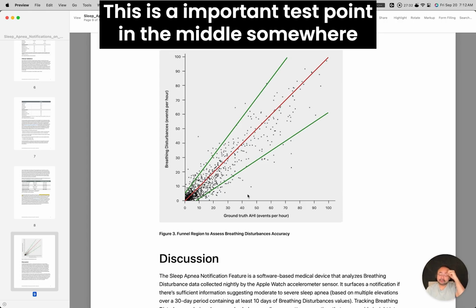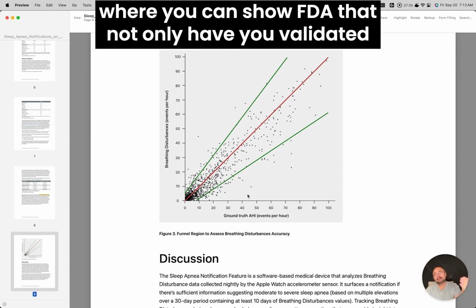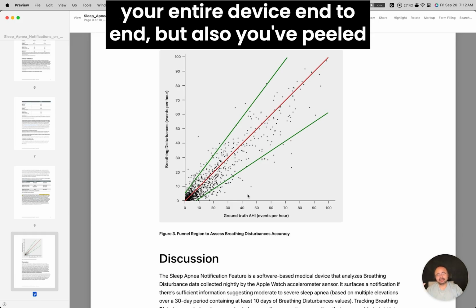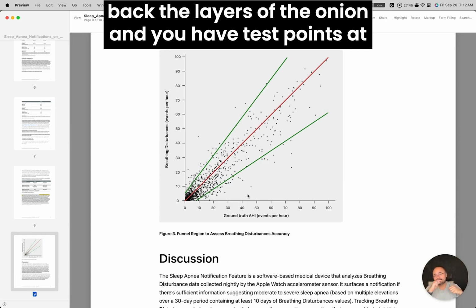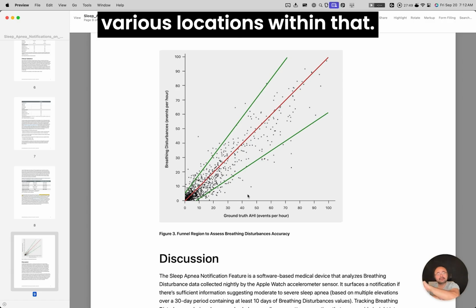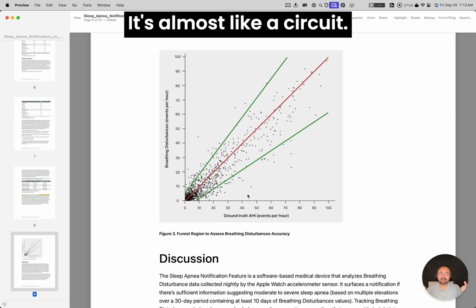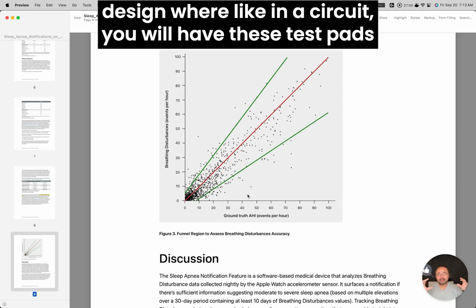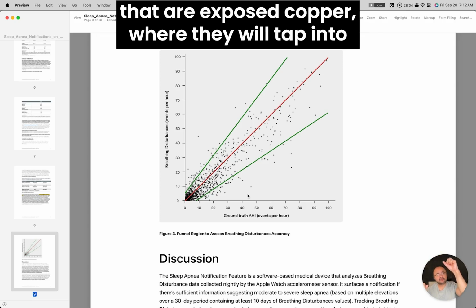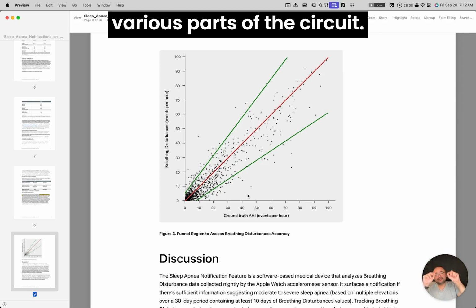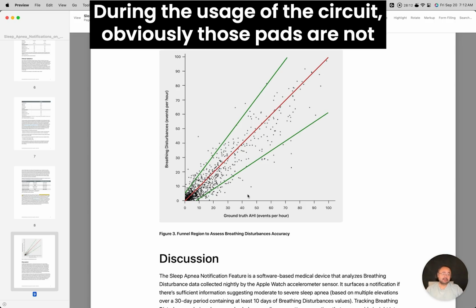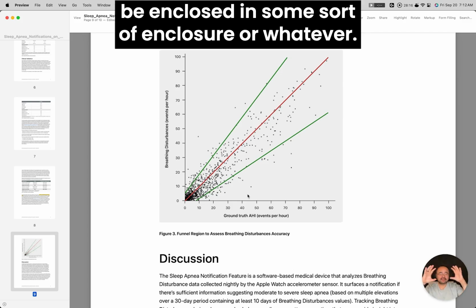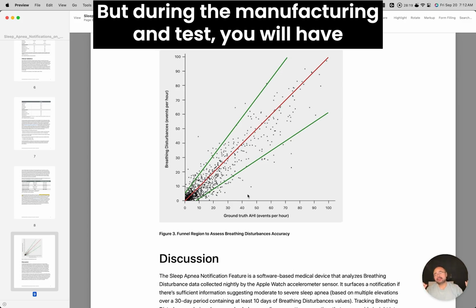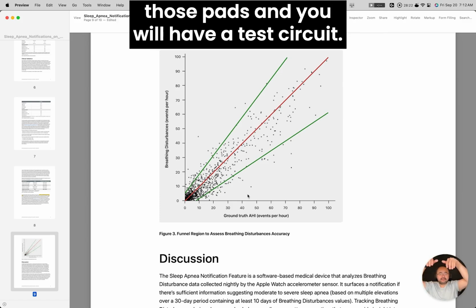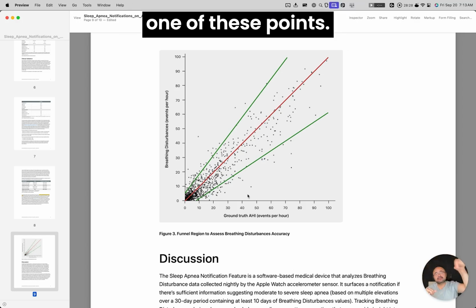This is an important test point in the middle somewhere where you can show FDA that not only have you validated your entire device end to end, but also you've peeled back the layers of the onion and you have test points at various locations within that. It's almost like a circuit design, where in a circuit you will have these test pads that are exposed copper, where they will tap into various parts of the circuit. During the usage of the circuit, obviously those pads are not going to be used because the whole thing is going to be enclosed in some sort of enclosure or whatever. But during the manufacture and test, you will have those pads and you will have a jig that comes in, probes and measures each one of these points.